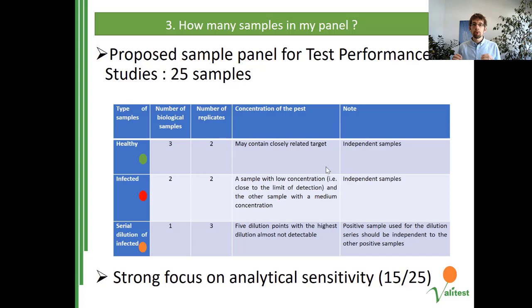The third group of samples is the serial dilution. We recommend using one sample with five dilution points, which are important because we can build a model to evaluate the limit of detection of the test. We also recommend using triplicates to evaluate the limit of detection. This sample must be different from the two infected ones. As you can see in this proposed panel, there is a strong focus on analytical sensitivity: 15 out of 25 samples are for analytical sensitivity.